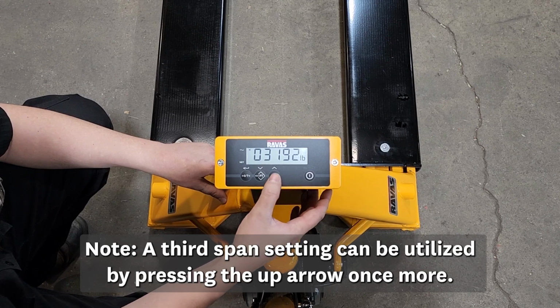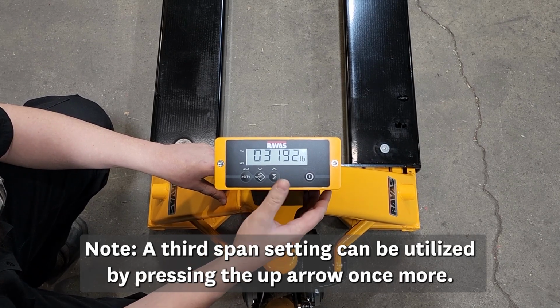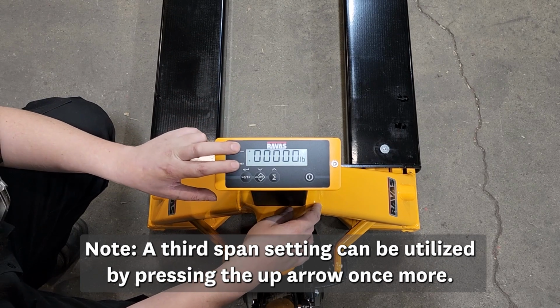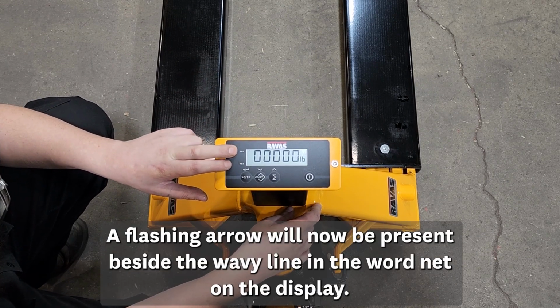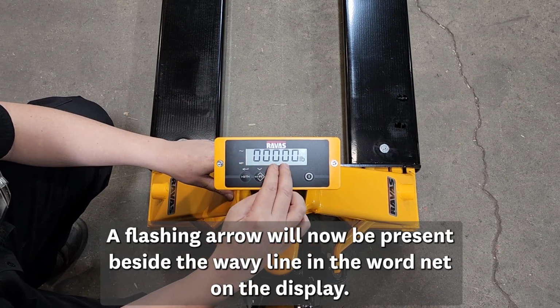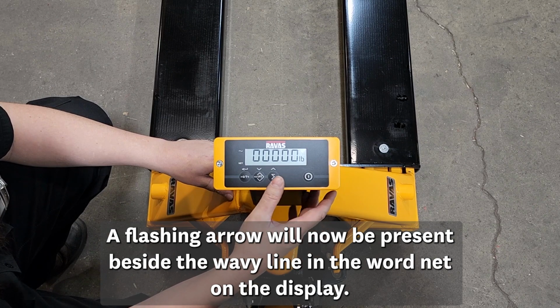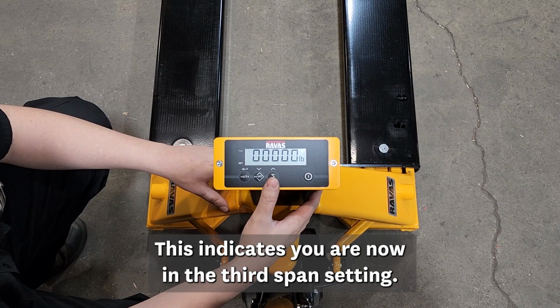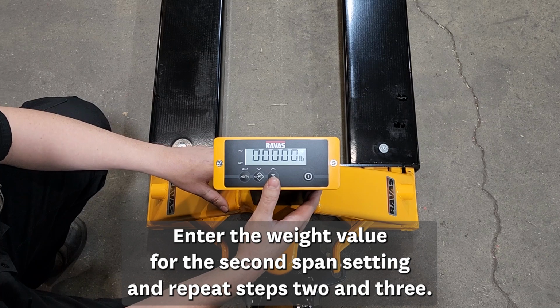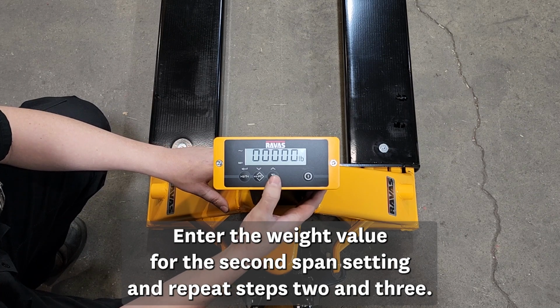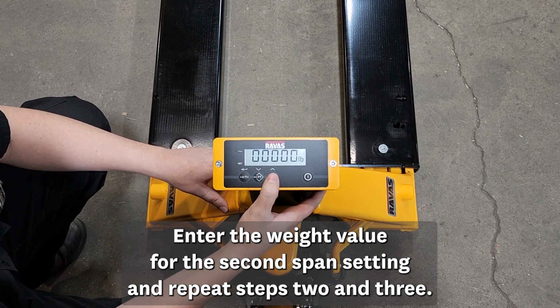Note: a third span setting can be utilized by pressing the up arrow once more. A flashing arrow will now be present beside the wavy line and the word net on the display. This indicates you are now in the third span setting. Enter the weight value for the second span setting and repeat steps 2 and 3.